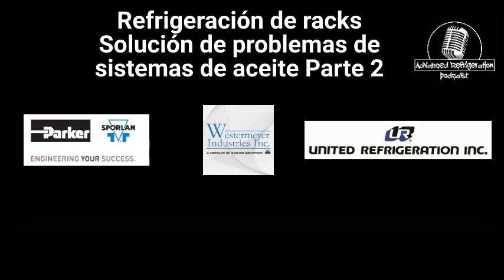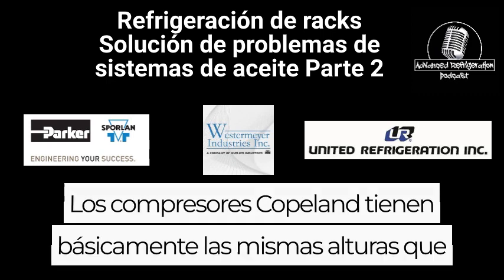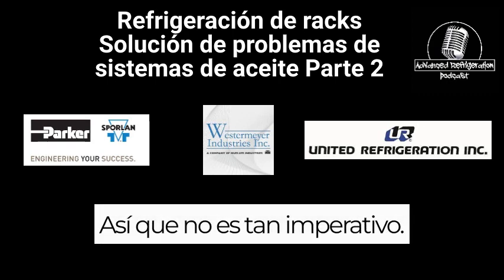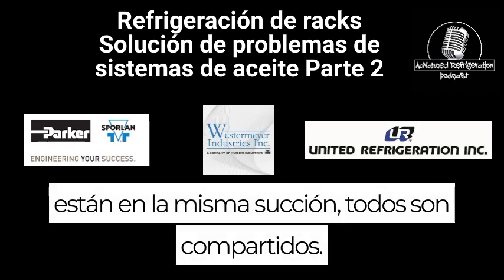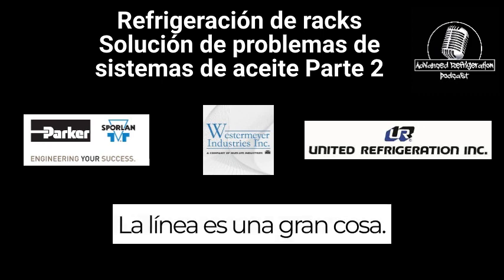Someone screwed up. The compressors actually have to be the same heights in the Carlyles. Copeland compressors are basically all the same heights as far as where the oil level control goes, so it's not as imperative. That's why typically those compressors, as long as they're on the same suction, are all shared. The purpose of the oil equalization line is a great thing.